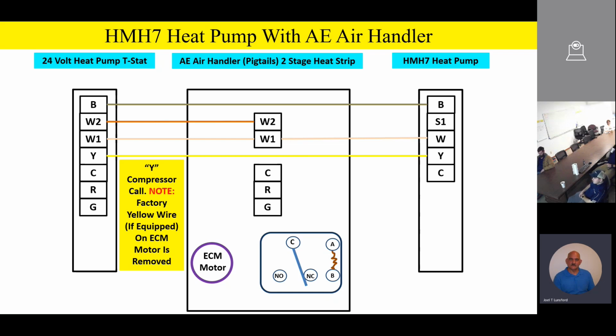Now watch this. We have a single Y terminal going outside, but the outdoor unit's going to modulate between 35 and 100% capacity. And what it does, it actually takes a look at outdoor air temperature. It looks at suction line temperature. It looks at liquid line temperature. It looks at discharge line temperature. It looks at suction pressure and so on. So it looks at 4 or 5 different sensors outside, and it's monitoring the refrigeration circuit as far as the pressures and temperatures on the suction line and so on. And then it makes intelligent decisions on what point of modulation or what point of capacity it's going to have. So really the real brains of the outfit, so to speak, is the outdoor unit. So the outdoor unit's going to be modulating according to these pressure and temperature parameters that it's actually measuring on the outdoor unit. So that's how it actually works.